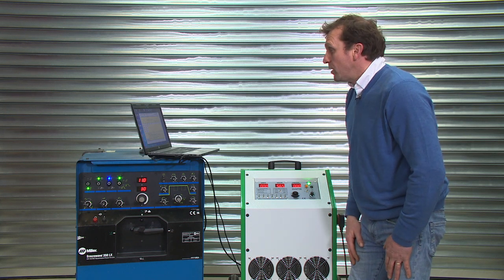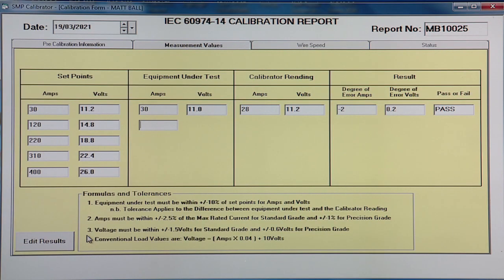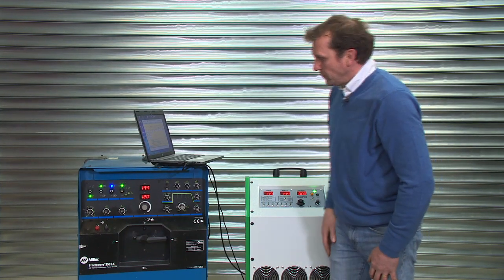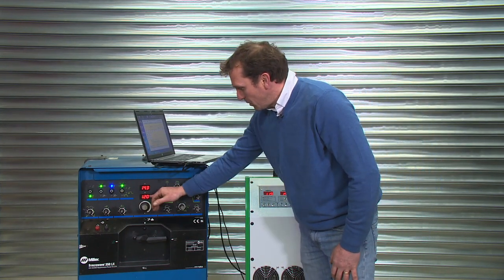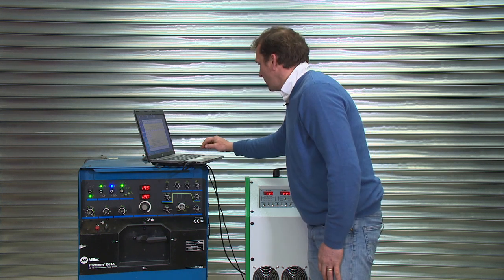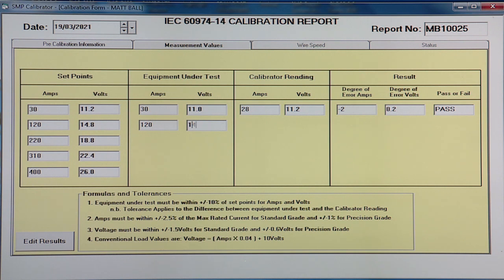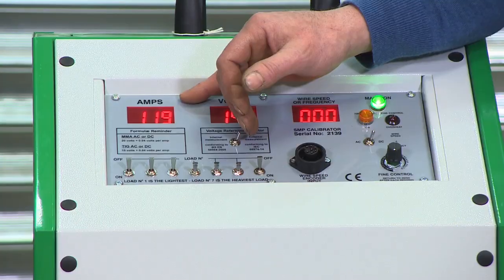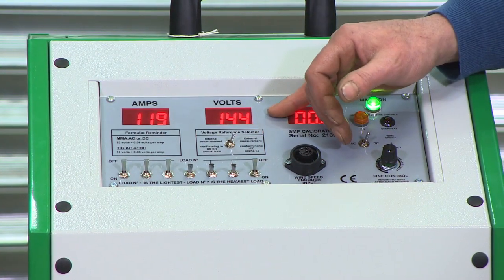Next reading, 120 amps, 14.8. We record 120, 14.3. And then the calibrator reading of 119, 14.4.